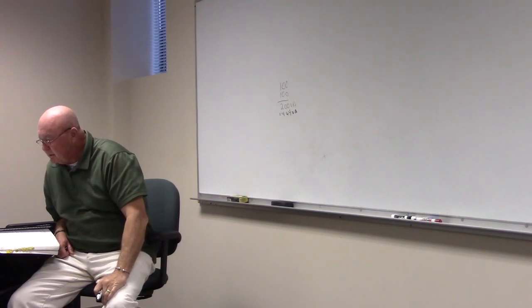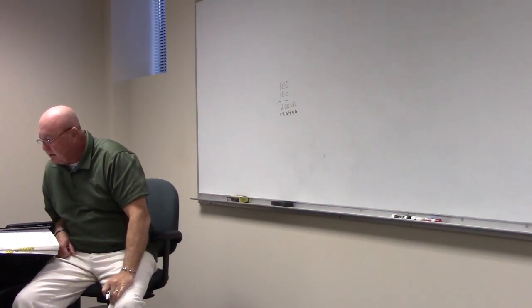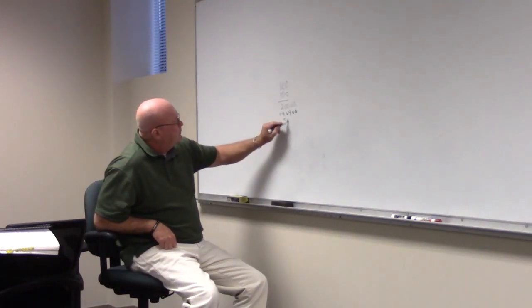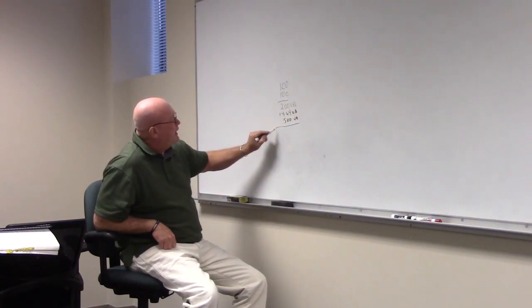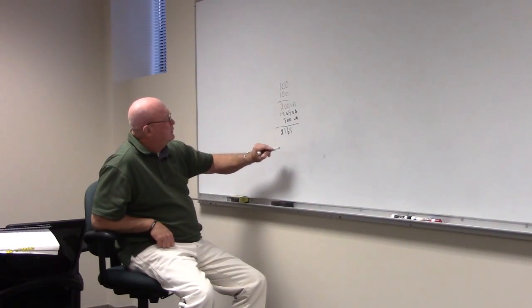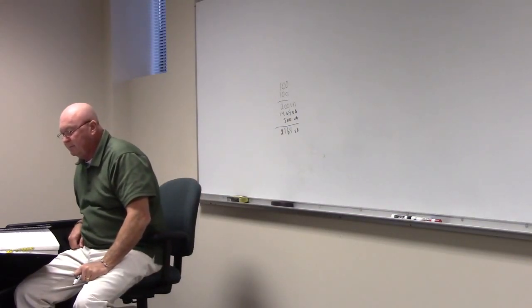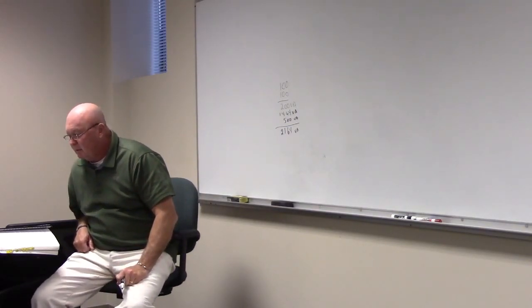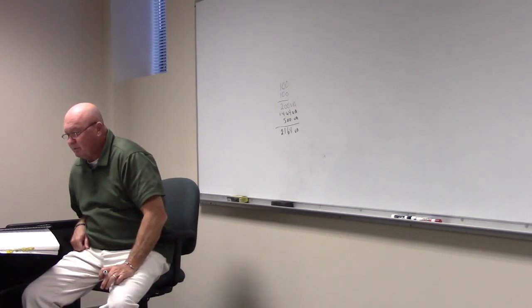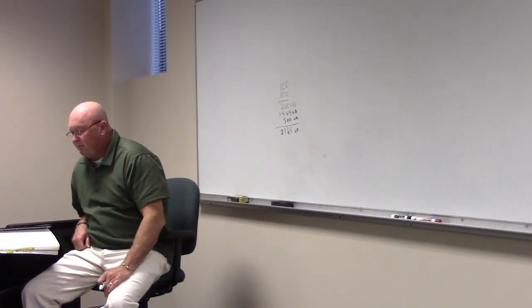All right. The other receptacle says electric cash register rated 300 and electronic calculator 200. So that's a total of 500 volt-amps. So now we just add these 3 together, and we get what? 2,164 volt-amps. Am I right there? Okay. And now, step number 3, we've got the total load so far. Step number 4 says you've got to do continuous load.